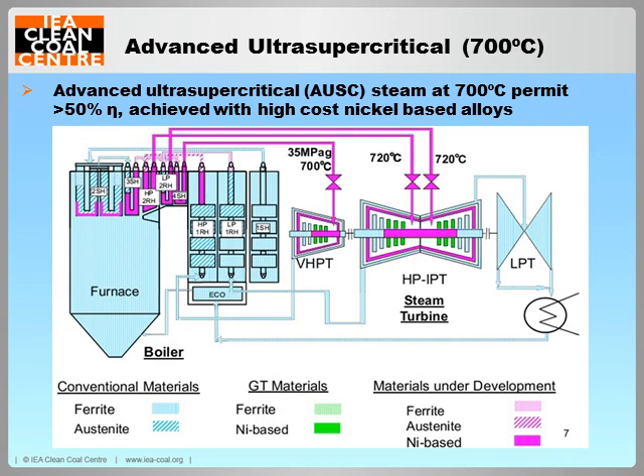As the steel barrier is estimated to be 650 degrees Celsius, nickel alloys can be used in place of steels in the highest temperature components to reach steam temperatures of 700 degrees Celsius, with efficiencies of over 50%. The location of these nickel alloys are highlighted on the flow diagram. There are large research programs in the USA, European Union, Japan, China, India and Russia which are researching nickel alloys. Although components manufactured from nickel alloys are 5 to 43 times more expensive than using steel, it is estimated that with superheater steam at 700 degrees Celsius and the corresponding rise in efficiency, the use of nickel alloys becomes economically favourable.